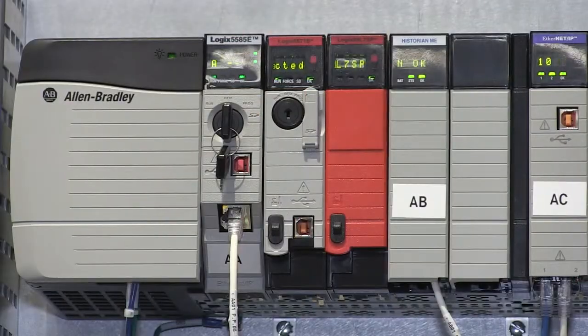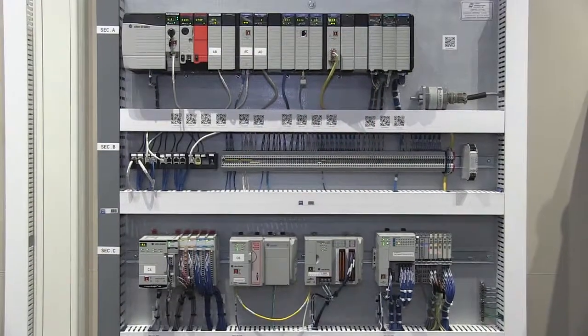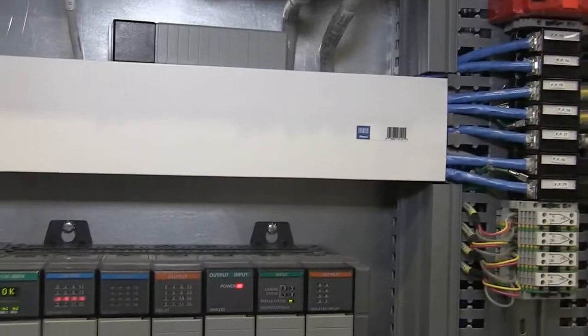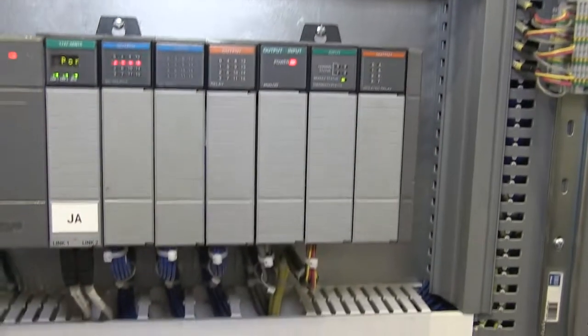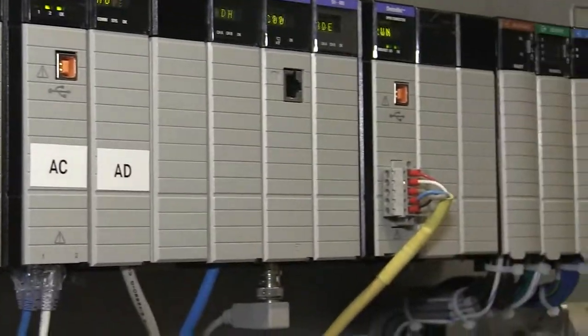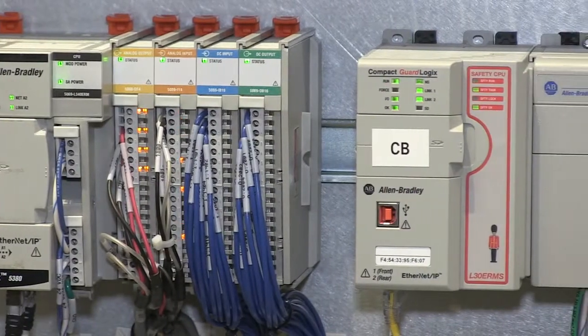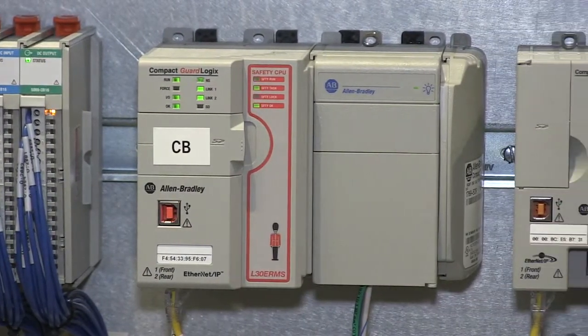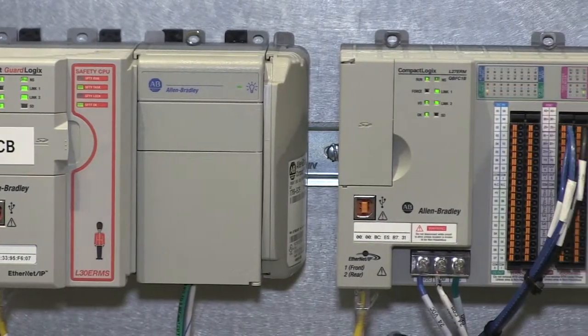I find IAB very helpful when helping a customer choose I.O. for a control system. For example, IAB will tell me if a given point I.O. rack is valid by ensuring proper power supply sizing and adding any necessary bus expansion power supplies. It also ensures a complete bill of material by including any end caps and terminal blocks required.